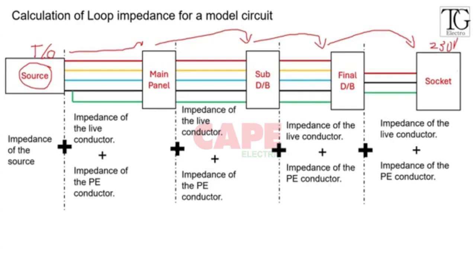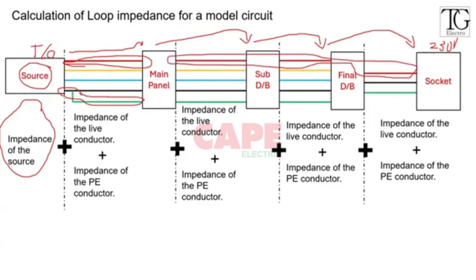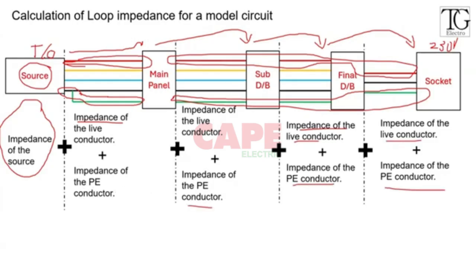To calculate the fault loop impedance, first you have to calculate the impedance of the source. I'll be showing you how to calculate it. Then you have to calculate the impedance of the line conductor. Suppose this is the line conductor, you are supposed to calculate its impedance. Like that, you calculate for all the line conductors, and you calculate the impedance of the whole PE conductor. So that's what I've written here: impedance of each line conductor, and you add it all with the impedance of the earth conductor. This is the basic philosophy. If you add all these values, you will get a value of Zs, in terms of ohm.